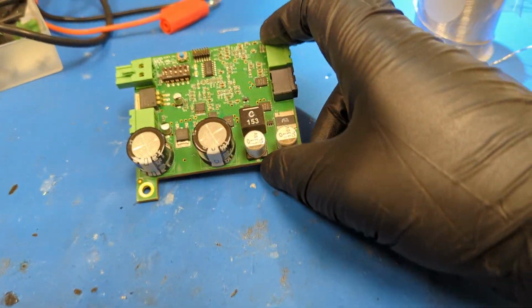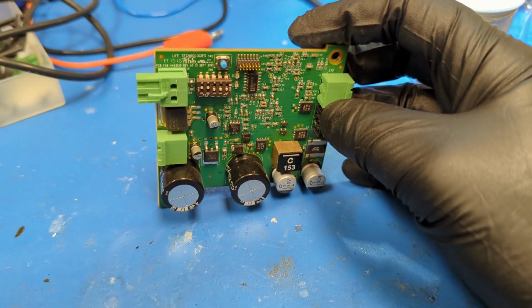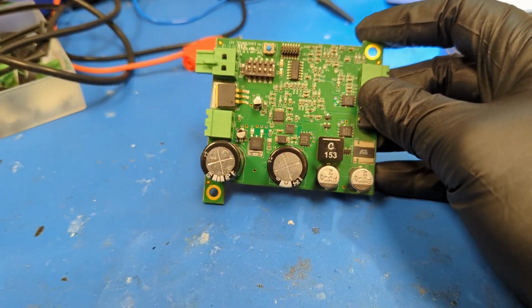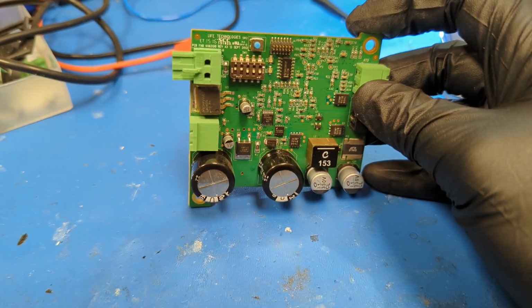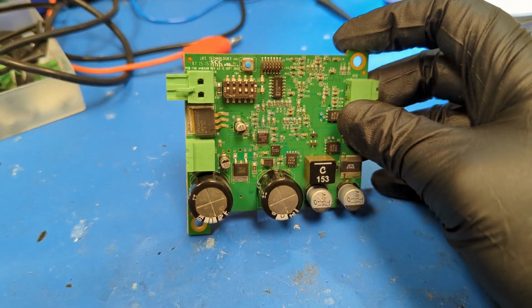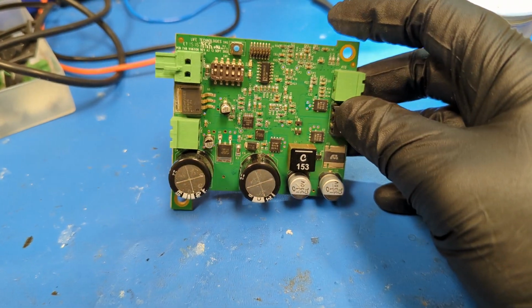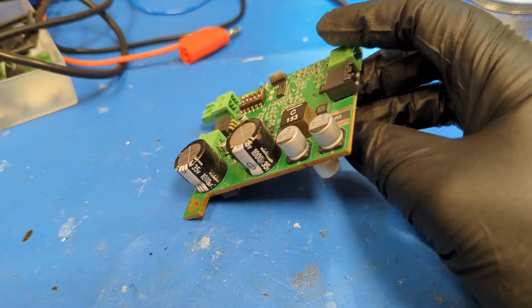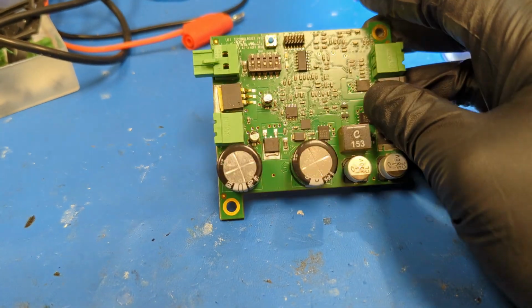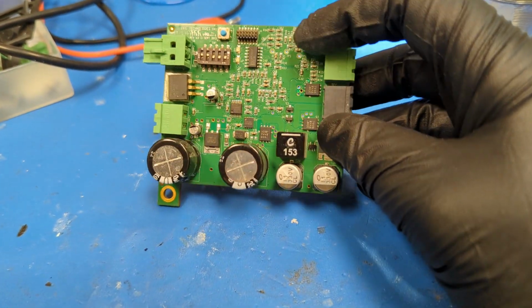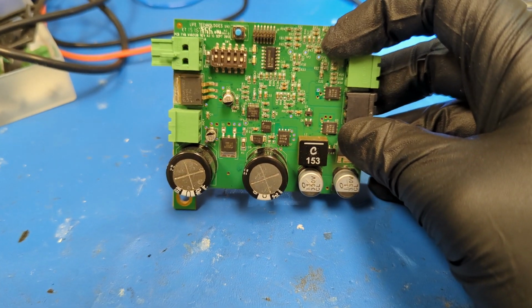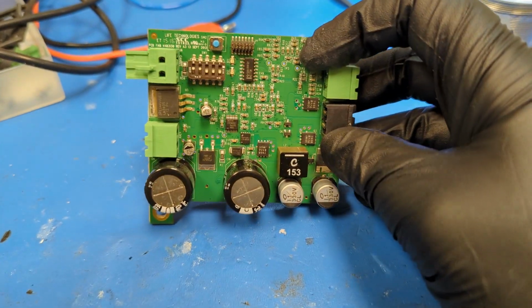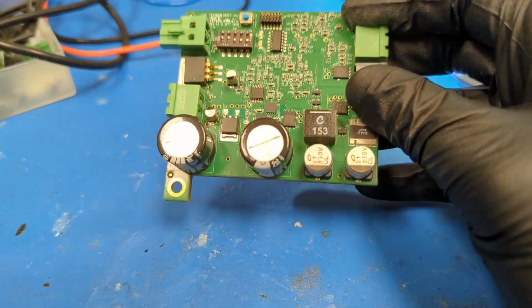Most equipment like this that does any type of temperature control will have a way to calibrate it, to set an offset value. That's common with PID controllers. So unfortunately, this doesn't have anything like that. You're not going to find any trim pots, and I forgot to go into what this is. This is the thermoelectric module for the SimpliAmp thermal cycler. There's actually 3 of these because you have 3 zones on the block, and I've got one here.